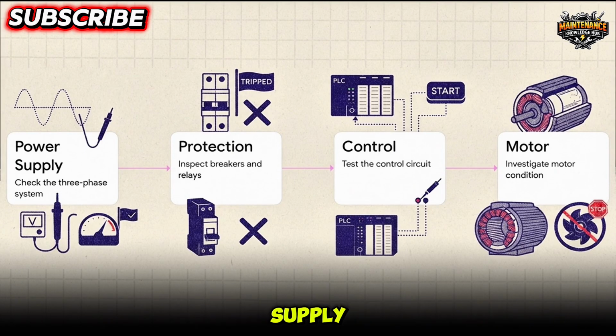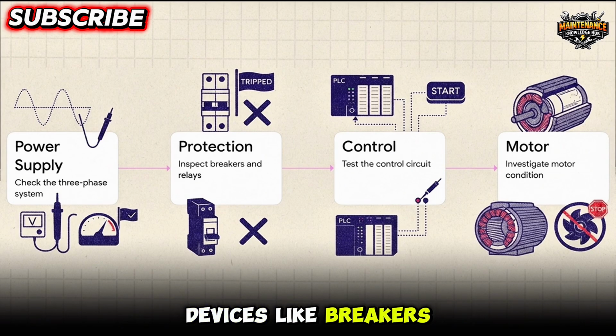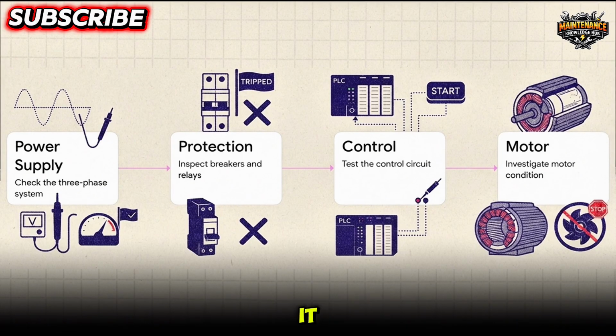First, check the power supply for things like phase loss or undervoltage. Then, check your protection devices like breakers or fuses. And here's a massive takeaway for your workflow. A repeatedly tripped breaker is a symptom. It is not a root cause, so stop resetting it. Next, trace the control circuit. Is control voltage even present? Is the start command actually coming through from the PLC? Finally, if all of that is perfectly healthy, you test the motor itself.